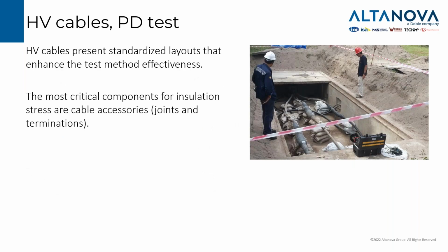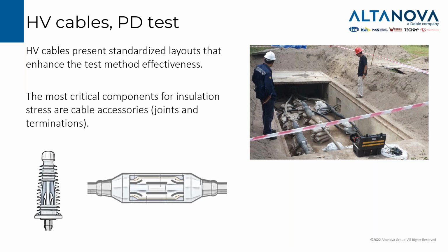We move now to the high voltage cable partial discharge testing. An advantage with respect to medium voltage PD testing is that in high voltage, the layout of the system, the components and the design are quite standardized. So we will always have some key points where we can decide to use our sensor. And there is more information about the installation and the commissioning of the cable. The most critical components for the insulation stress in high voltage cable are the cable accessories, typically joints and terminations. And we are quite lucky because in high voltage cables, these accessories always have their own detection point, be it the ground lead of the termination or the link box of the high voltage cable joint.